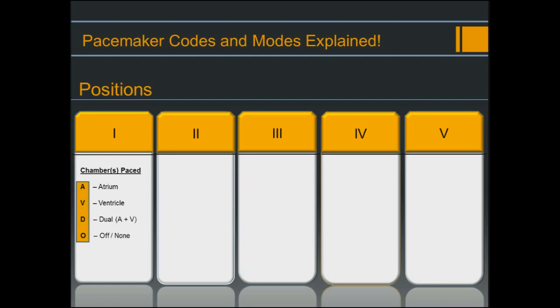Now that we have a little history, let's talk about the code. The code is made up of positions — five to be exact. Each position is assigned a letter letting you know where and how the pacemaker is going to behave. The first position represents the chamber or chambers being paced: A for atrium, V for ventricle, D for dual (meaning A and V), and O for off.